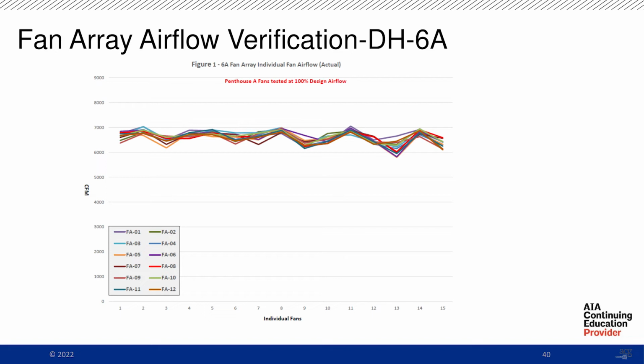Here are some more examples, comparing to after they made their bracing and cone adjustments. With our mechanical contractor out there, it's night and day, and that makes it easy for us. When we find an issue, if someone's available, it was taking about a day or 2 for them to get it fixed. That's awesome.